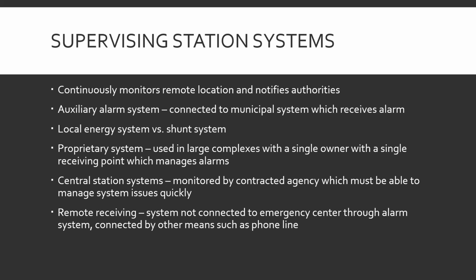Proprietary system. It's used in large complexes with a single owner, with a single receiving point, which manages alarms. This is like a really big hospital, maybe an older hospital, or a big paper mill, a big factory where they've got on-site security 24/7, keeping an eye on things, and all the fire alarm systems go to the security office where there's always a guy there.